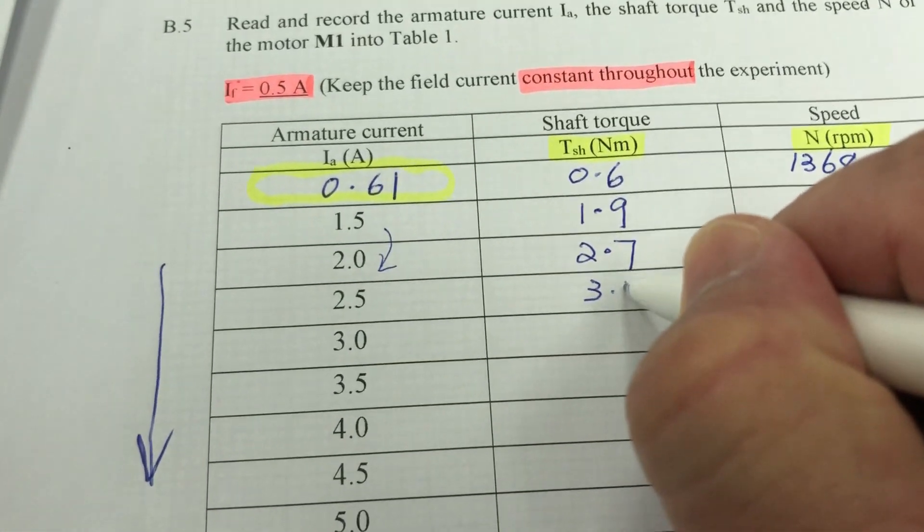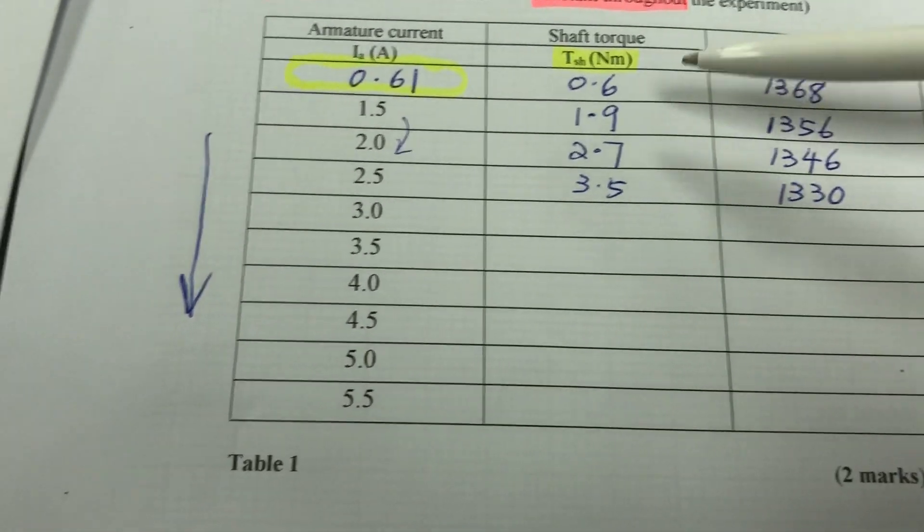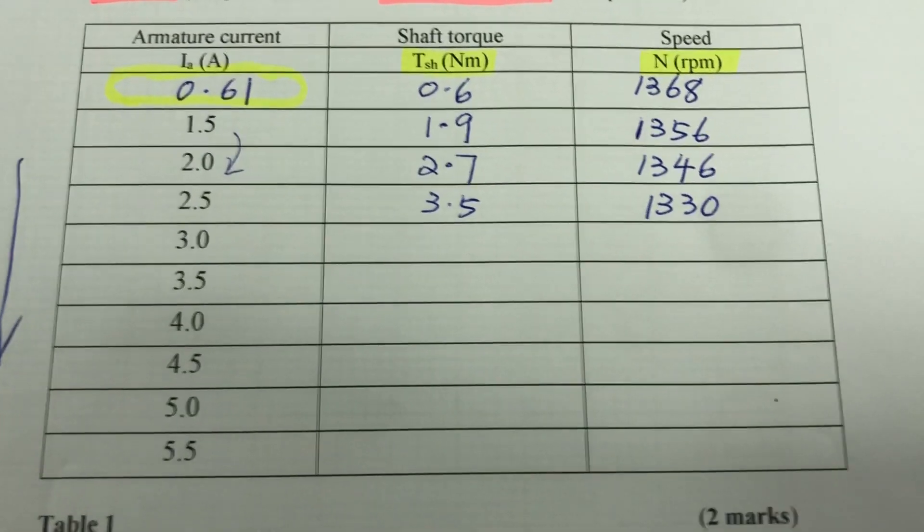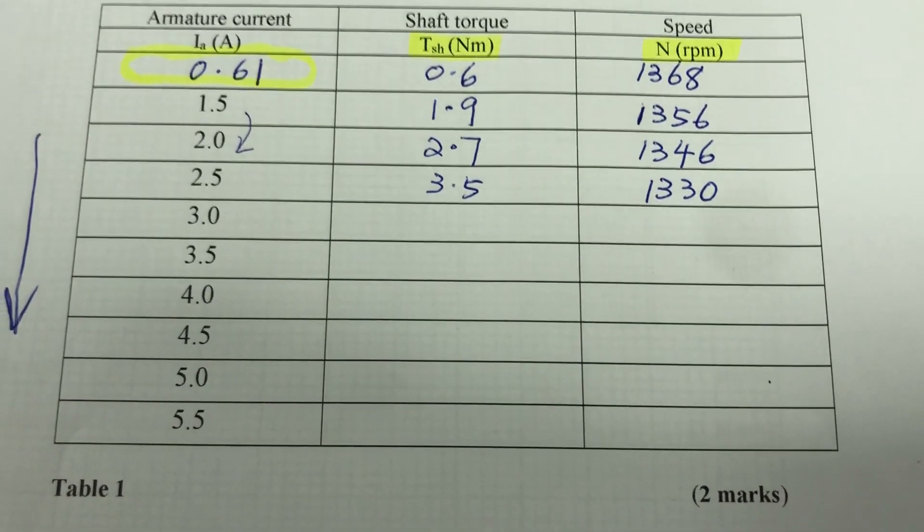Okay so 3.5 Newton meter and 1330 RPM. Okay this will go right to the end until it is 5.5 ampere armature current, the rated value. So I'll stop the recording here.